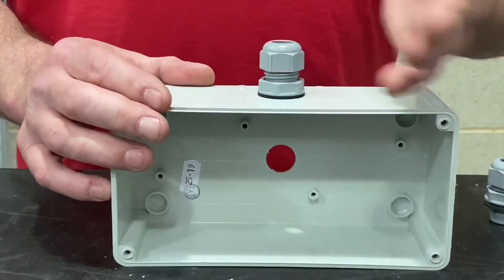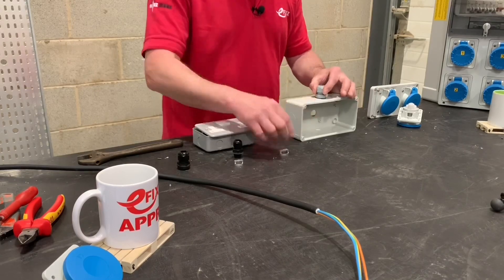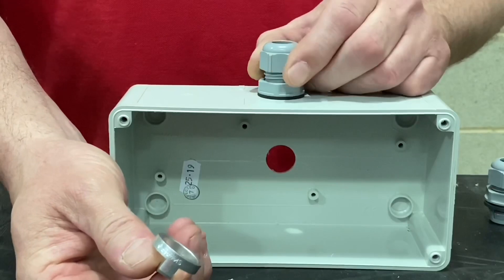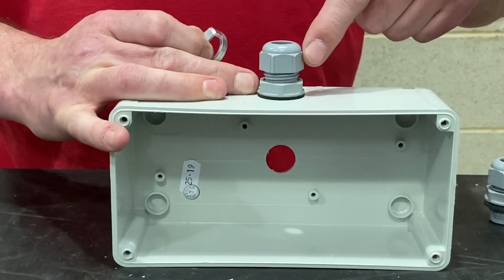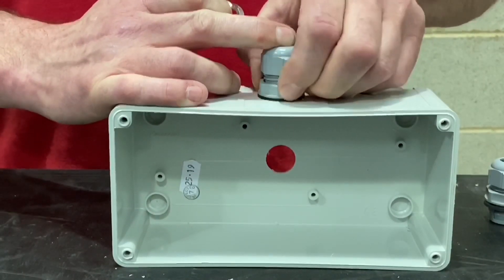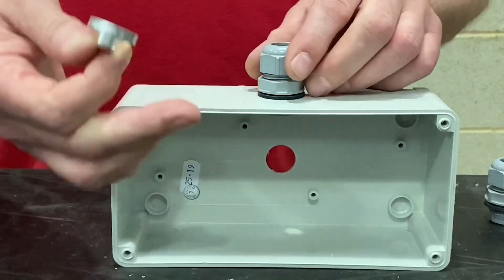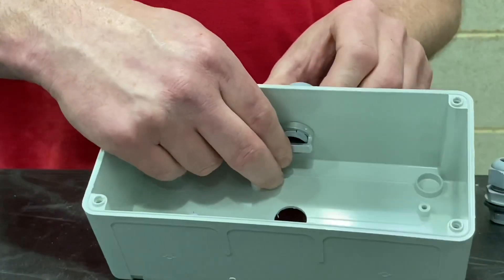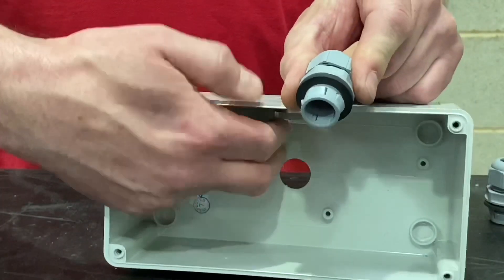This is probably considerably faster than installing a standard gland. But there may come a point where you need to take this back out — that's where this little releasing tool comes in handy. We back off the nut by going anticlockwise to loosen it until it stops. Then we push the releasing tool onto the gland fully into position and lever it out. Super simple — released instantly with those two bits of kit.